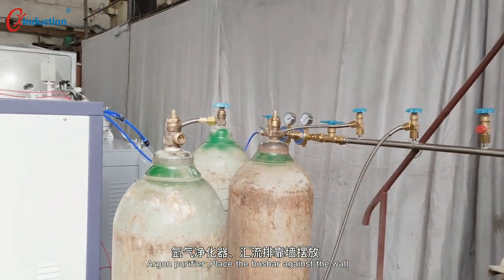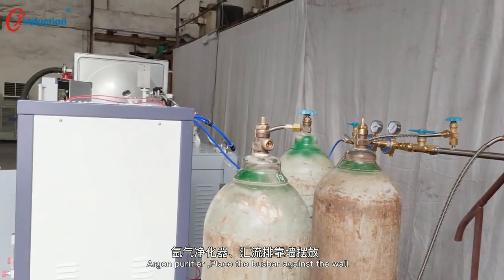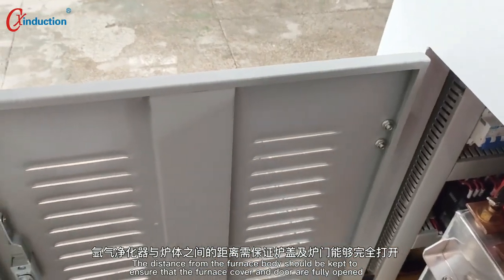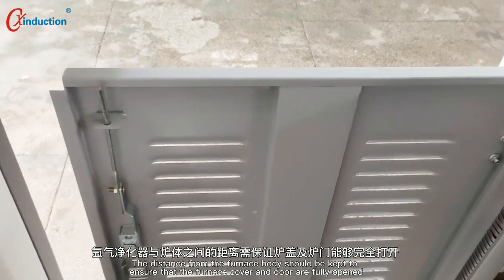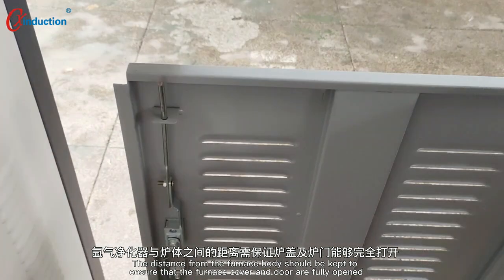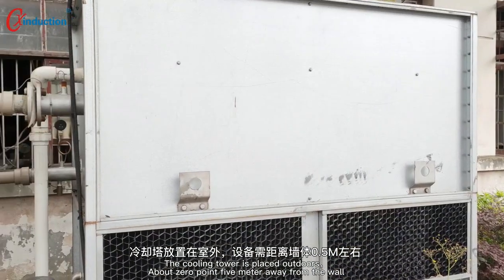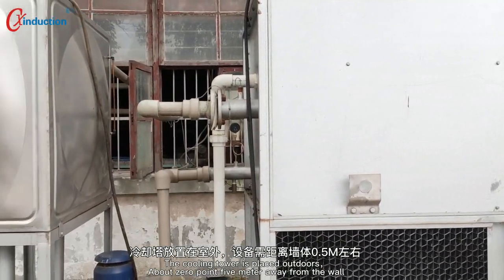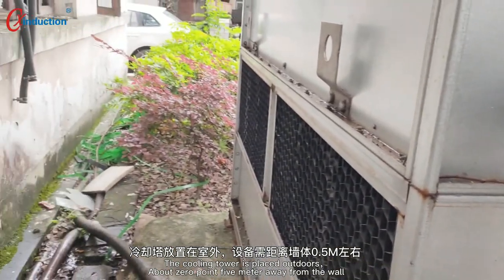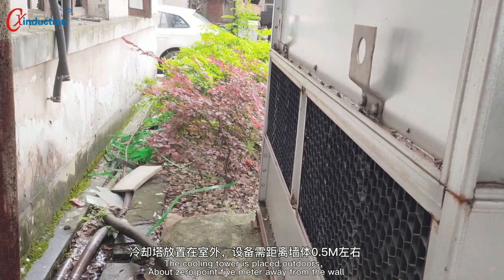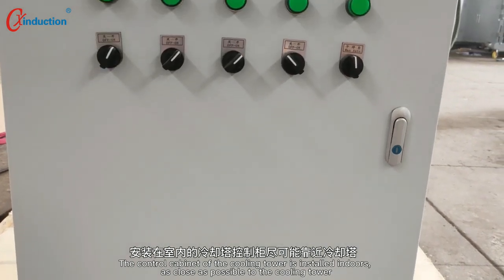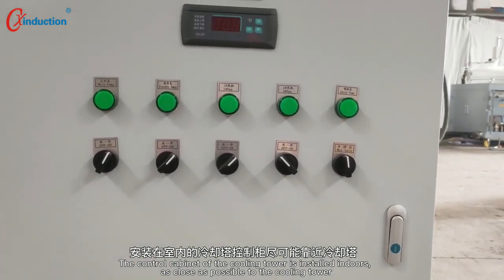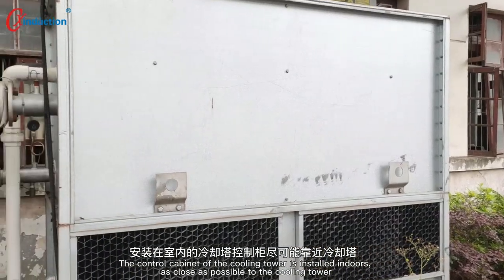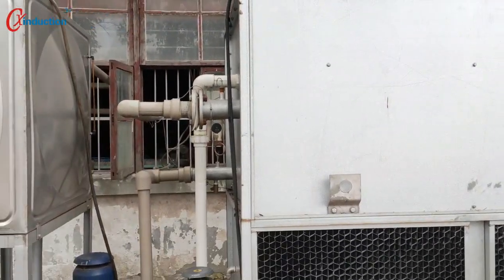argon purifier. Place the busbar against the wall. The distance from the furnace body should be kept to ensure that the furnace cover and door are fully open. The cooling tower is placed outdoors, about 0.5 meter away from the wall. The control cabinet of the cooling tower is installed indoors, as close as possible to the cooling tower.